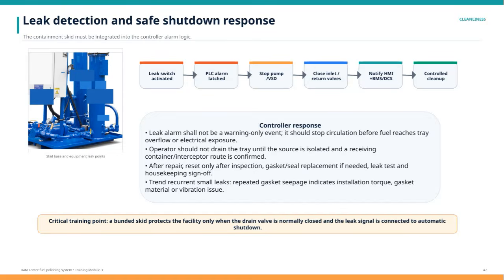Here we focus on leak detection and the corresponding safe shutdown response. The key point is that the containment skid must be integrated into the controller alarm logic to ensure a coordinated and effective reaction to any leaks. First, cleanliness is critical, especially around the skid base and potential leak points in the equipment. When a leak is detected and the leak switch is activated, the system triggers an alarm within the PLC, which then latches to hold the alert state. Once the alarm is latched, the controller initiates a safe shutdown sequence.